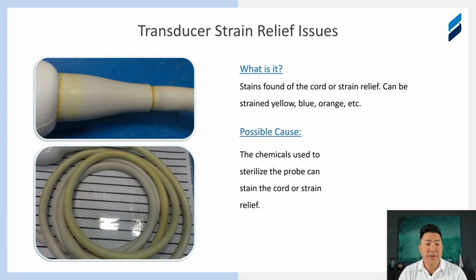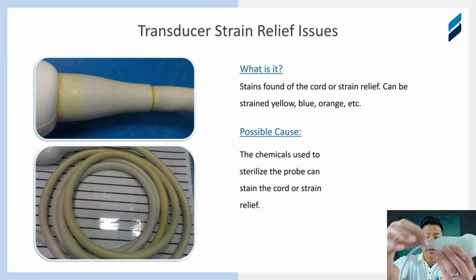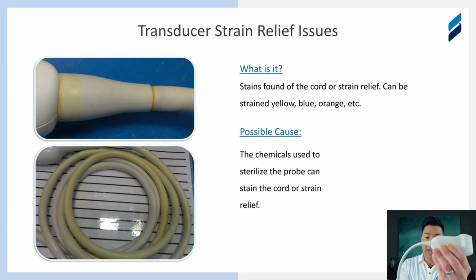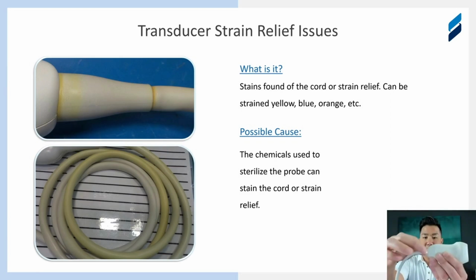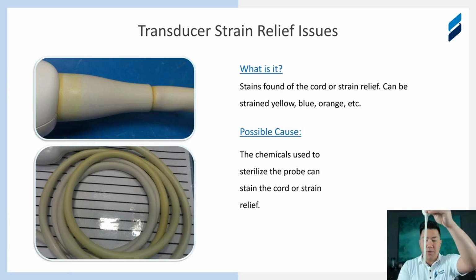What we have here is some issues around stains, strain reliefs, and cords of transducers. So if I have a transducer here, we're talking about the strain relief that is between the cable itself and the body of the probe, and even the cord sheath, which is the cable here on the outside. What we want to chat about is that there's a lot of chemicals used to disinfect these transducers after a use on a patient to get ready for the next one. And sometimes they can stain these rubbers that are on the probe here. And it's very repairable. This is something that doesn't really impact performance or patient safety.